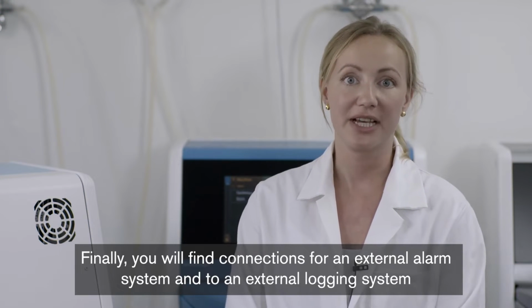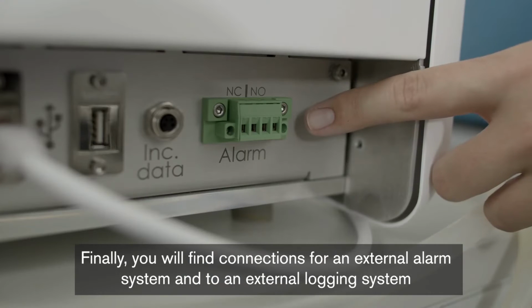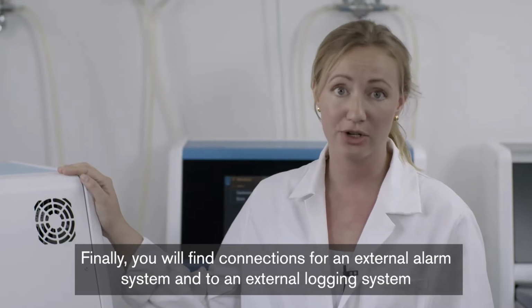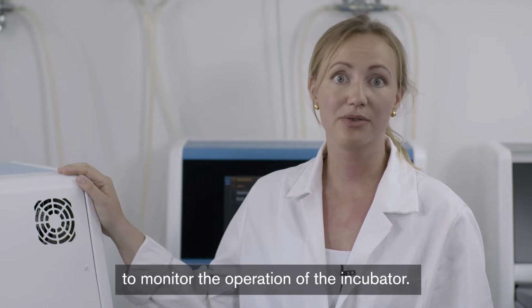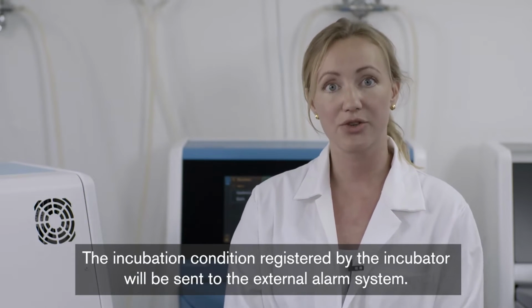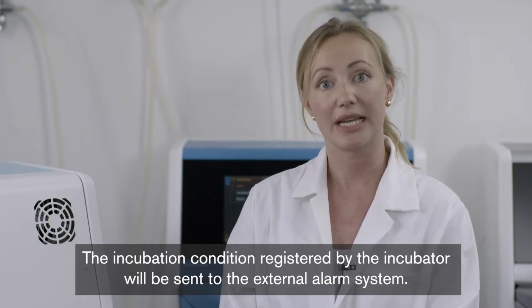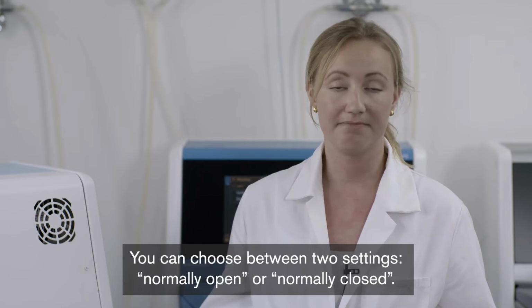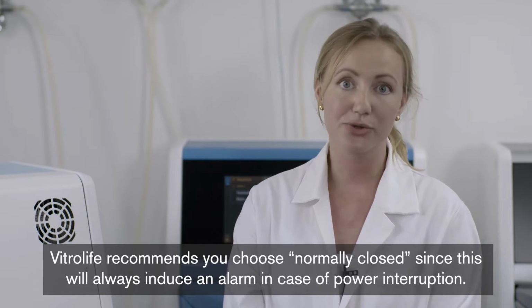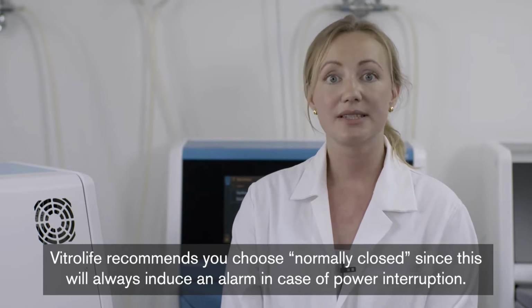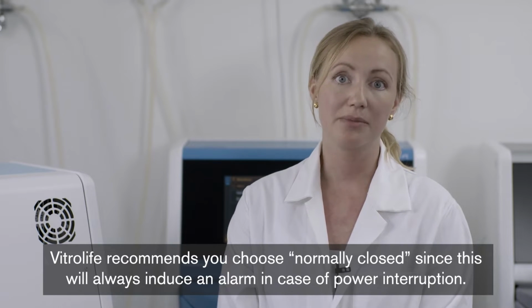Finally, you will find connections for an external alarm system and for an external logging system to monitor the operation of the incubator. The incubation conditions registered by the incubator will be sent to an external alarm system. You can choose between two settings, normally open or normally closed. Vitrolife recommends you choose normally closed, since this will always induce an alarm in case of power interruption.